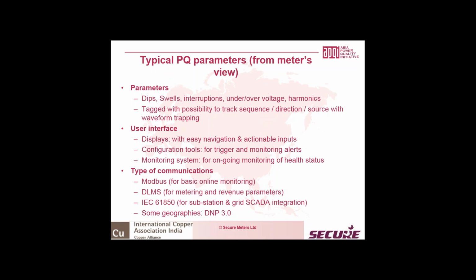The user must also have displays and configuration tools along with the monitoring system so that he is able to track the accidents, the shutdowns or the problems which he is facing in his plant back to what has happened in the last 10 minutes on my supply side. So, were there any transients or were there any interruptions? For that, a monitoring system, which preferably should be online, is required. Nonetheless, if it is missing, the meter usually records all these events in its memory and then it can be taken up for analysis offline also.